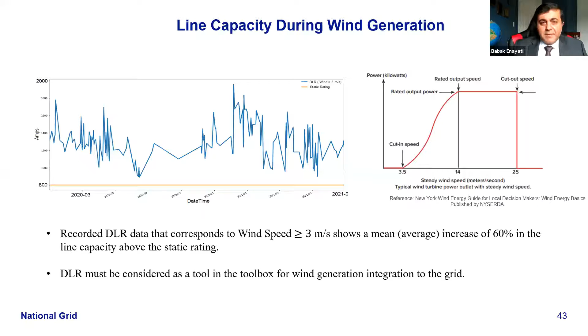However, even without considering wind speed, you may install a DLR on a transmission line and see that the DLR never goes below static. That's another chance to increase the static rating in planning. However, the adoption of DLR in operations is more likely than in planning, because of the inability to forecast future temperature.